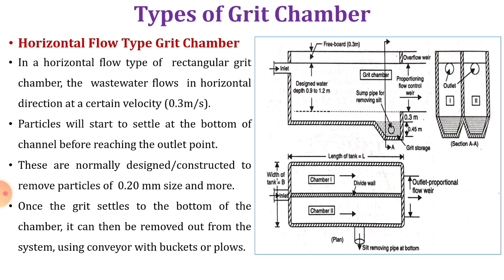Horizontal flow grit chambers are normally designed to remove particles of 0.2 mm size and more, so larger-size particles are removed. Once the grit settles to the bottom of the chamber, it can then be removed from the system using a conveyor with buckets or plows.